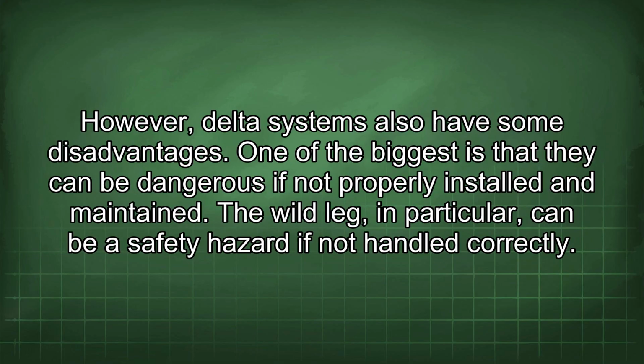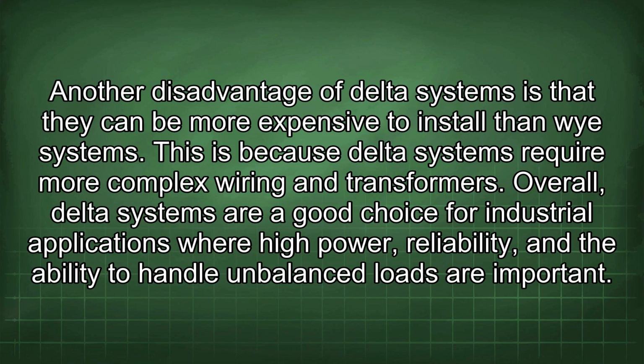However, delta systems also have some disadvantages. One of the biggest is that they can be dangerous if not properly installed and maintained. The wild leg, in particular, can be a safety hazard if not handled correctly. Another disadvantage of delta systems is that they can be more expensive to install than Y systems. This is because delta systems require more complex wiring and transformers.